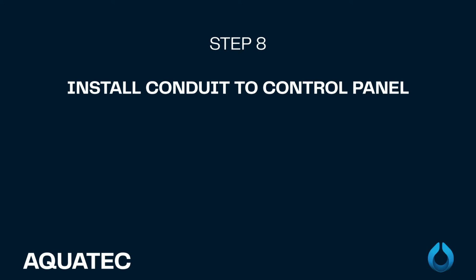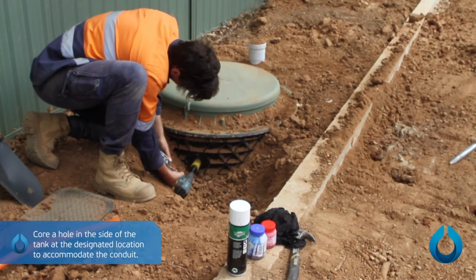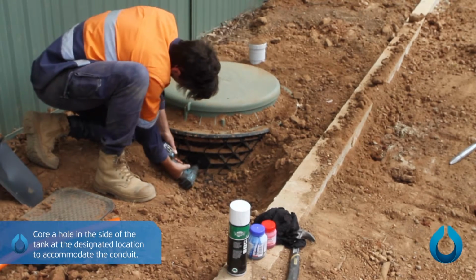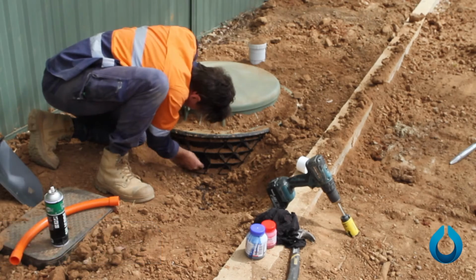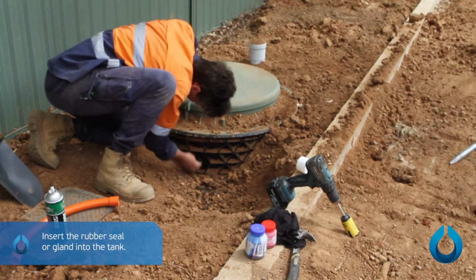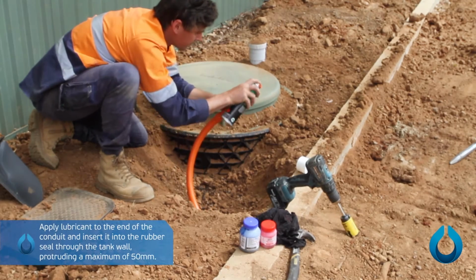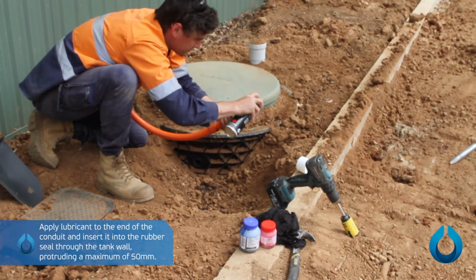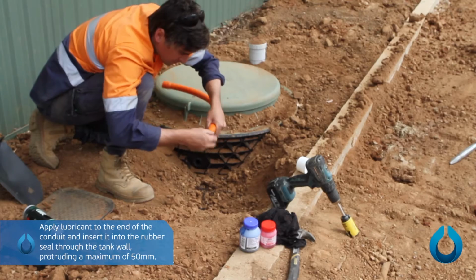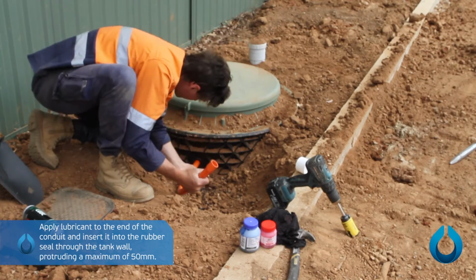Step 8. Installing the conduit to the control panel. Core a hole in the side of the tank at the designated location to accommodate the conduit. Insert the rubber seal or gland into the tank. Apply lubricant to the end of the conduit and insert it into the rubber seal through the tank wall, protruding a maximum of 50 mm.